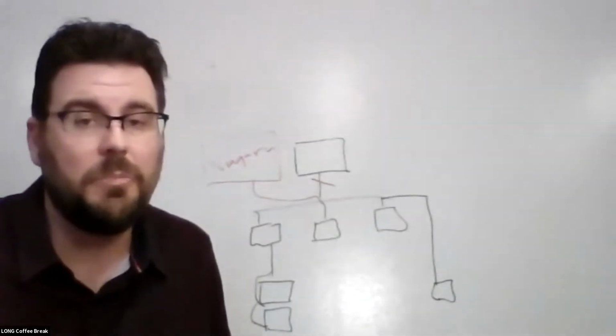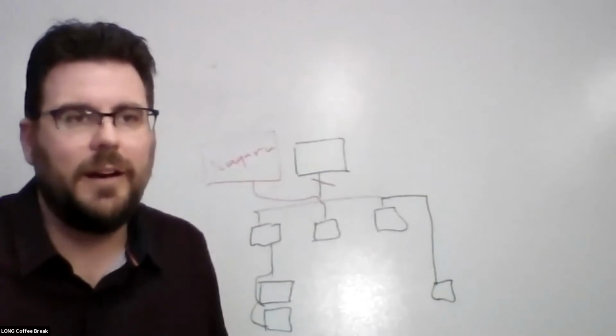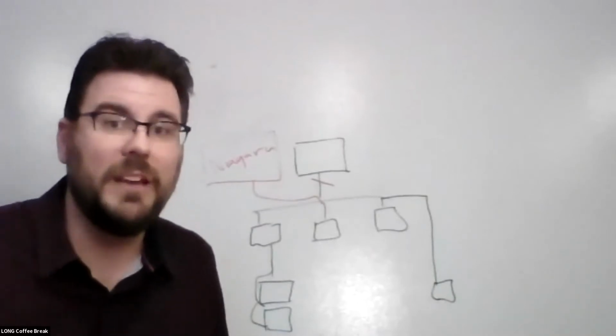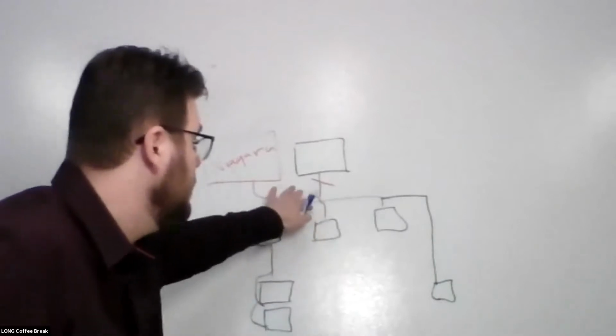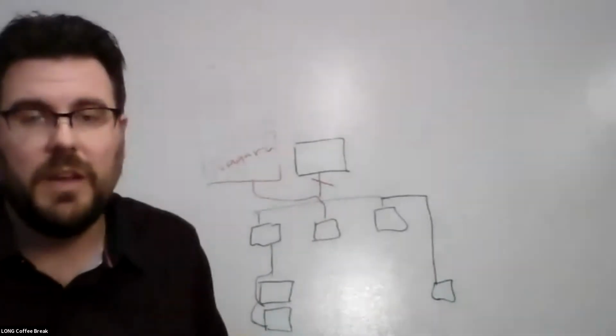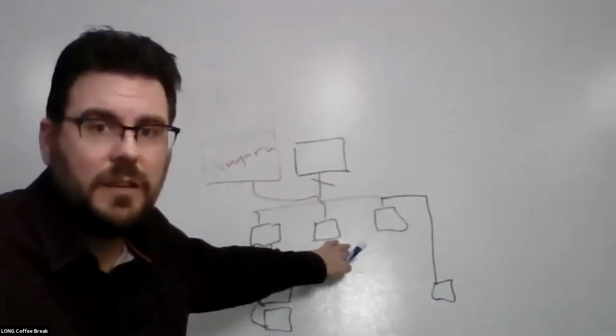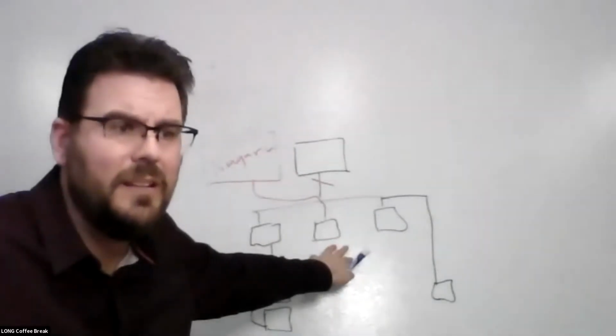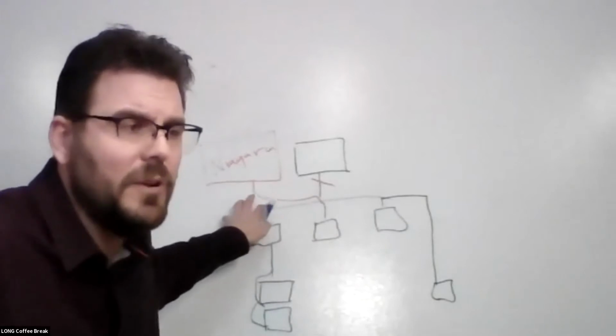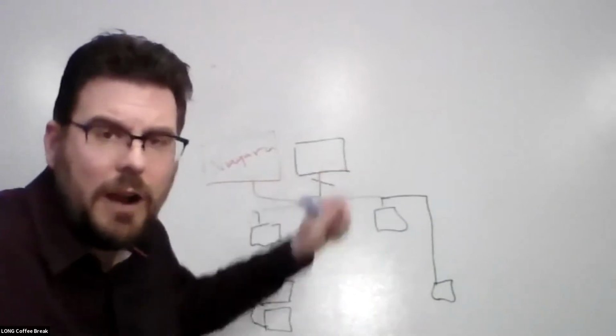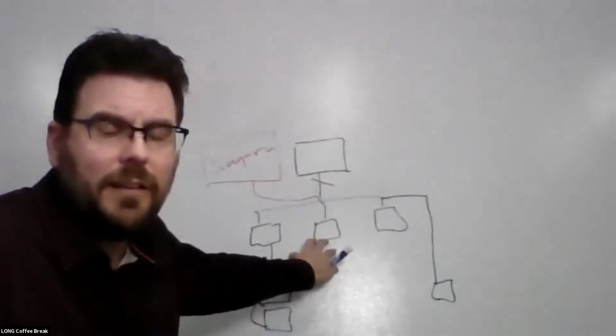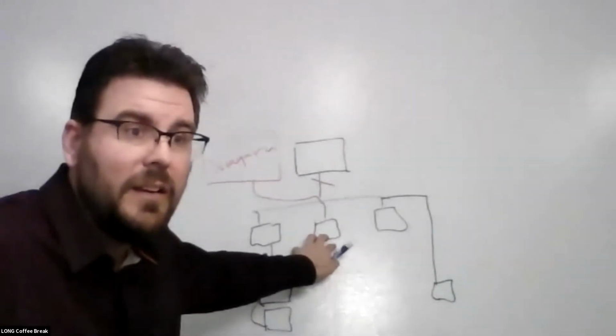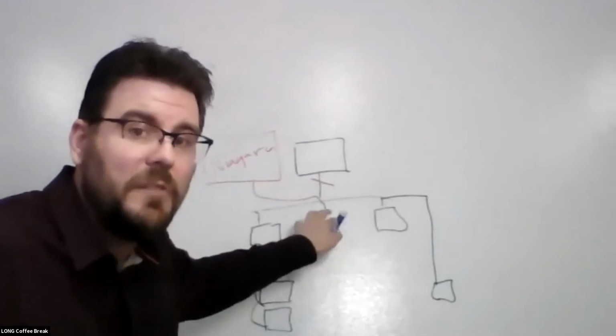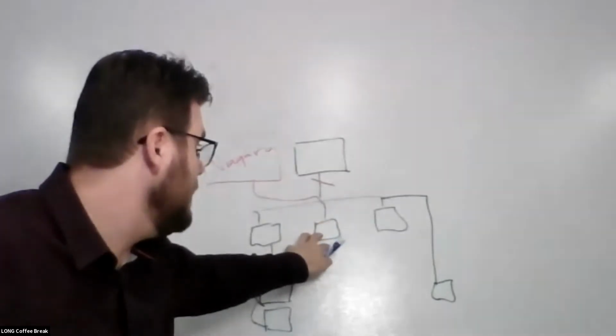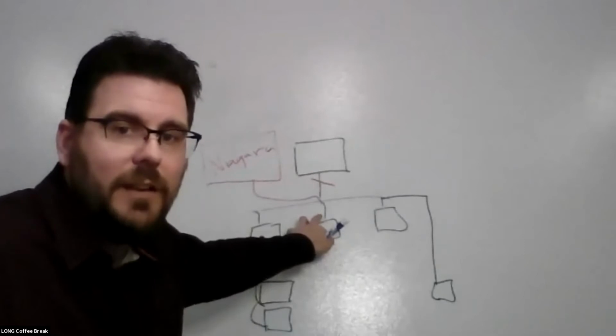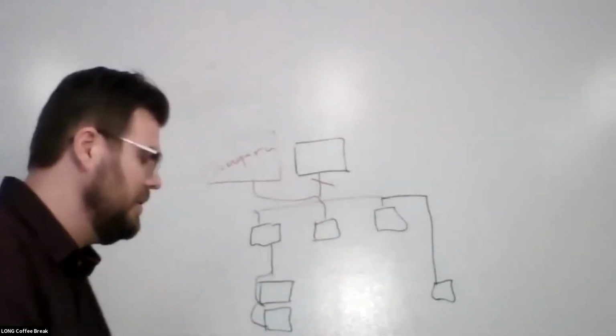If you're talking proprietary protocols, there are a lot of options for protocol integration drivers that can be put in place to start to pick up the protocols from these. If they're already BACnet MSTP, we can easily convert them to BACnet IP with a driver or a router. If it's already BACnet IP or MSTP, sometimes, and with some of the controls providers out there, they can actually firmware upgrade and flash upgrade this particular device.